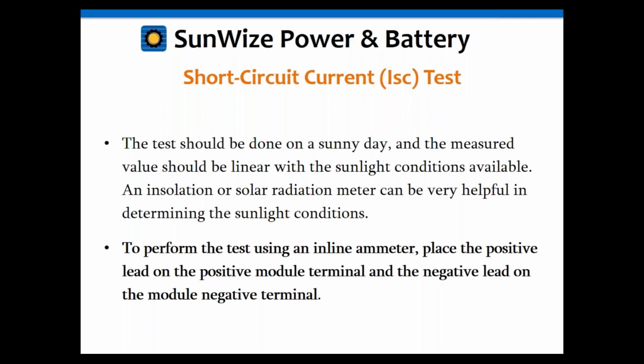But if you have a small solar module to begin with, on a cloudy day or a non-ideal day, and its maximum short circuit current is only about 2.5 amps, and you have a meter that's only accurate to within a half amp, that could be off by as much as a half an amp, and that's not so good. So I usually prefer an inline meter. Again, it's also the easiest way to do the short circuit. That way you don't have to put an additional wire in there.